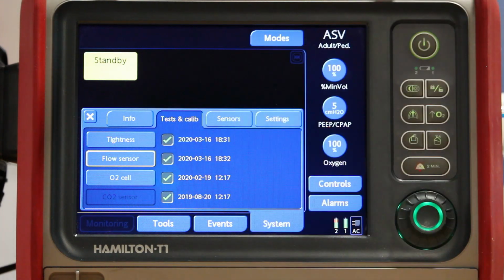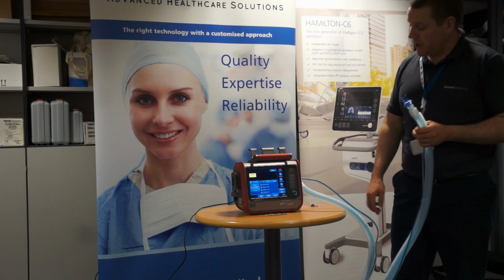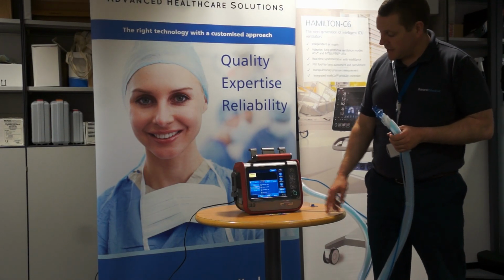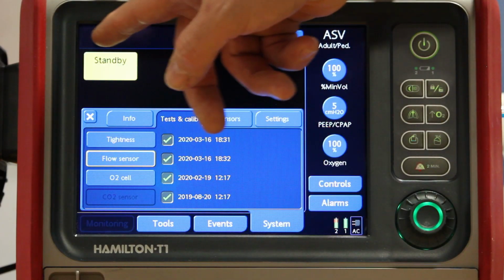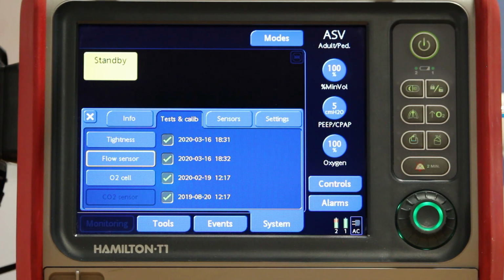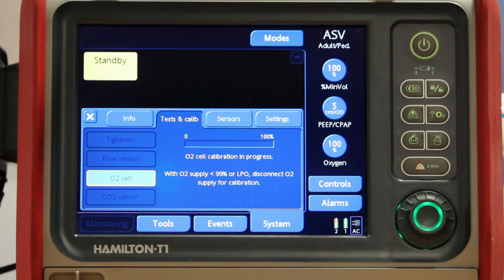The third one then is the O2 cell calibration. You don't need to do it every time, you only need to do it when you're prompted by the ventilator, and you'll be prompted with a red X and a yellow alarm text up on top to say O2 cell calibration needed. And if you are prompted, all you do is you press the O2 cell button. It'll calibrate the O2 cell in the background. You don't need to do anything else. You could be doing other preparation at this point. This takes 2 minutes.